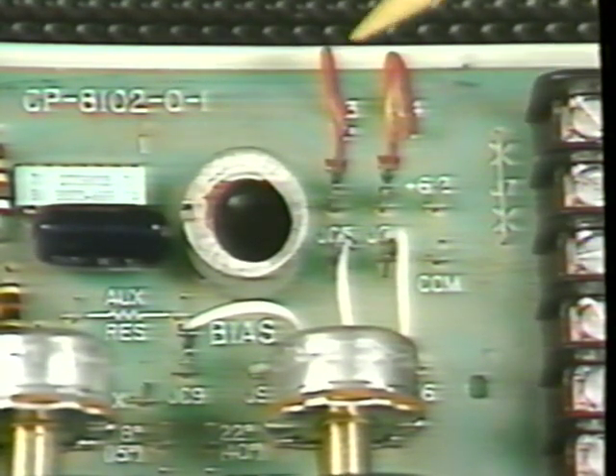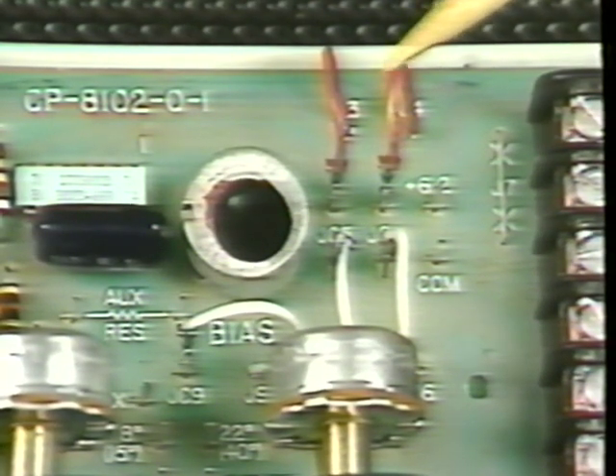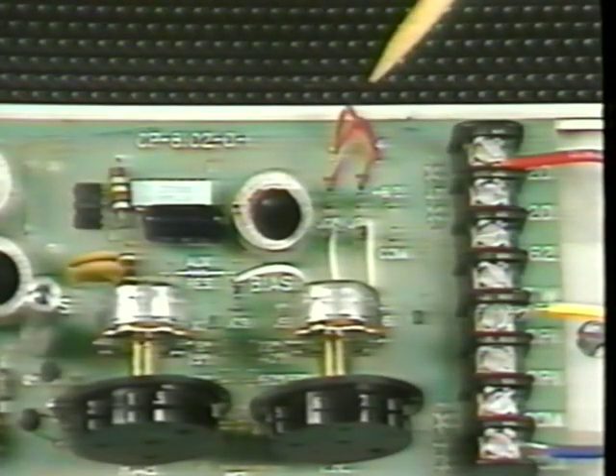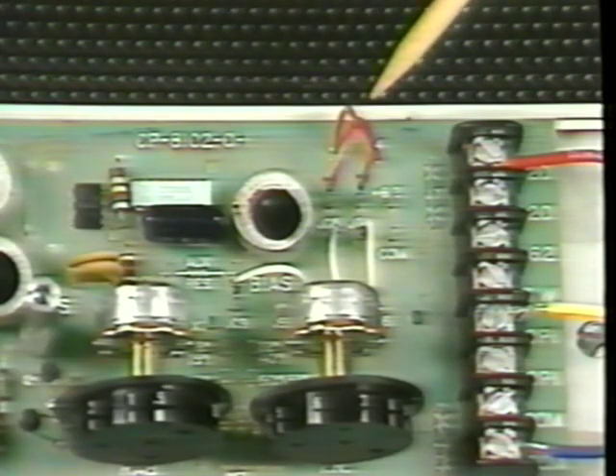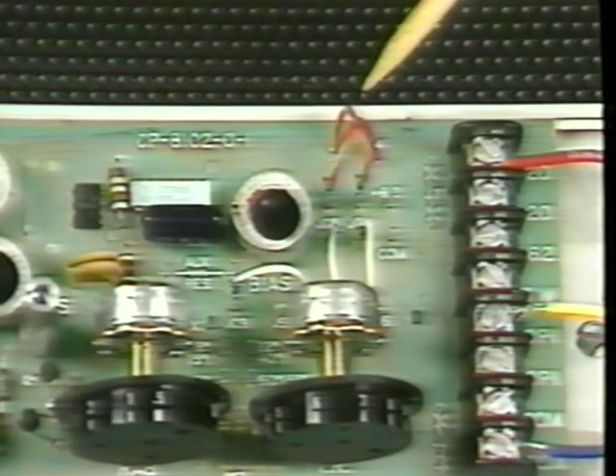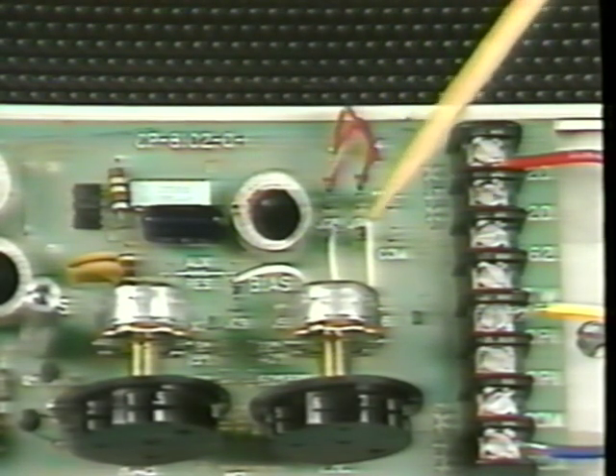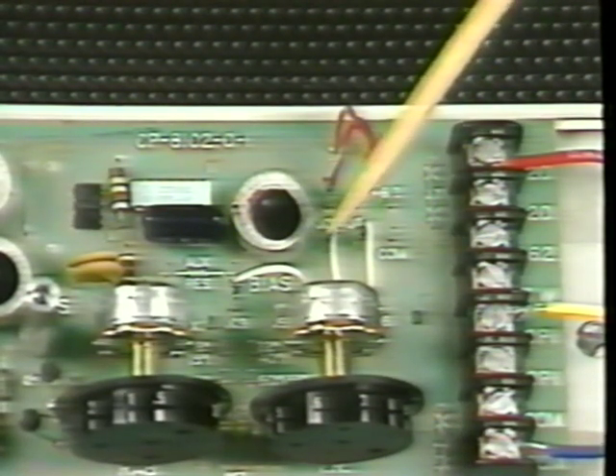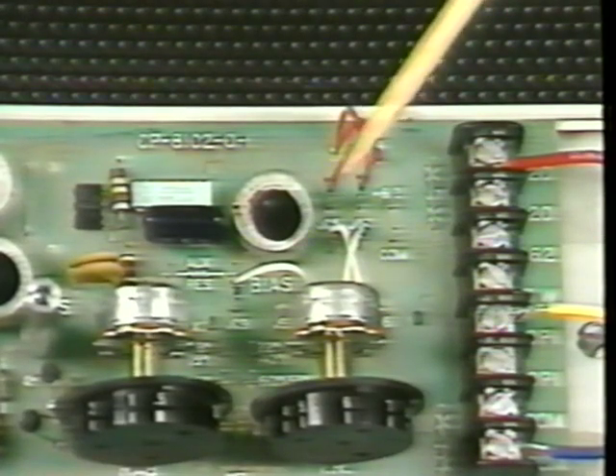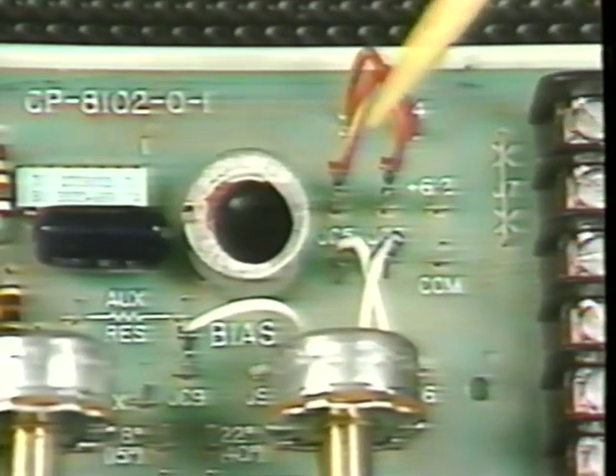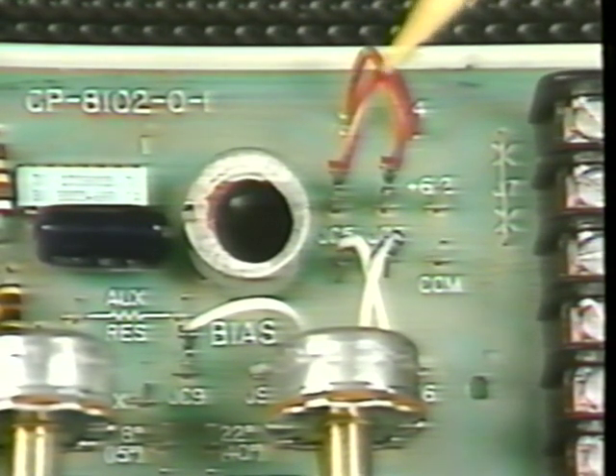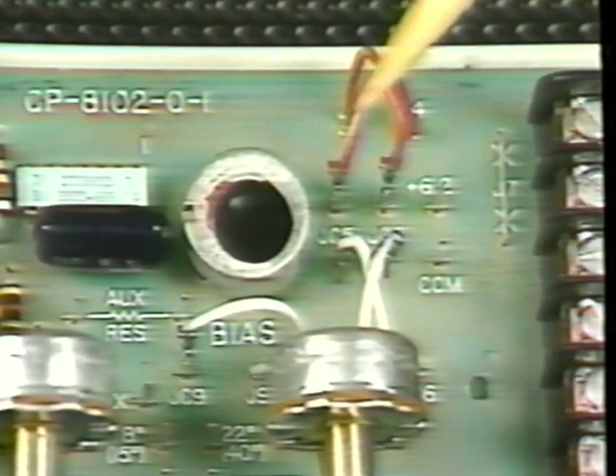If our application requires normally closed valving, then just the reverse is required for control. Now our controller is reverse acting. As the hot water temperature rises, our signal will fall, allowing a normally closed valve to go closed. However, we still want reverse reset, so the second pair of jumpers must be readjusted to match the first. Remember, when the two jumper pairs match one another, the reset is reverse. When the two pairs are different, the reset is direct. Hot water reset, based on outside air temperature, is an example of reverse reset.